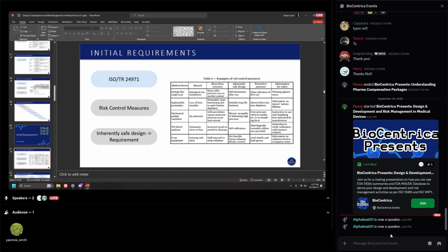And then the third will be purely on the training side. So it can be incorporated into your labeling, your user manual. It's either user manual or labeling or both. I will recommend both because there can be some circumstance where someone reads your label but doesn't read the user manual or vice versa. Typically, what you have on your labeling is also included in your user manual anyway. So these are the three basic levels of how to mitigate a risk.